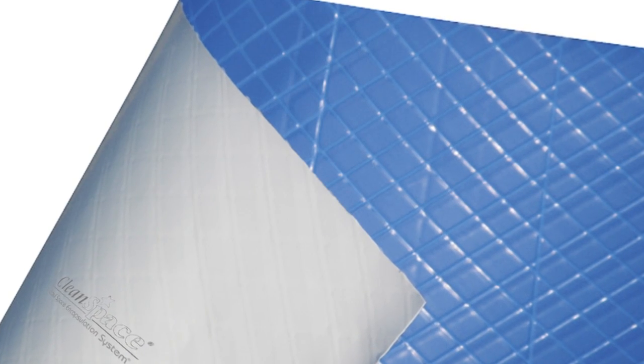What we do is we use a product called CleanSpace. It's a 20 mil thick, fiber-reinforced, antimicrobial product that we cover the floor of the crawl space with. It's a very thick material — like a pool liner — and we seal the seams, we go up the side walls, and we caulk the top of it. Really what we're doing is sealing out any moisture coming from the walls or from the soil, separating the crawl space from those damp areas.